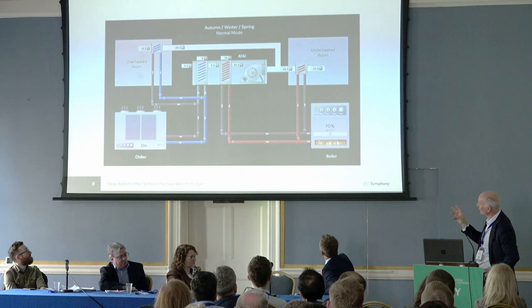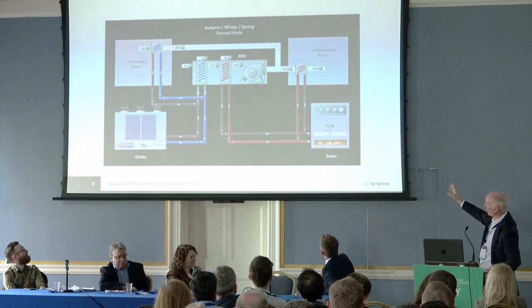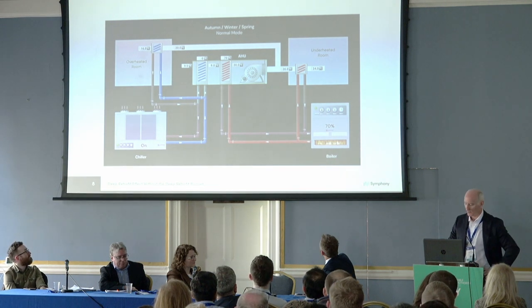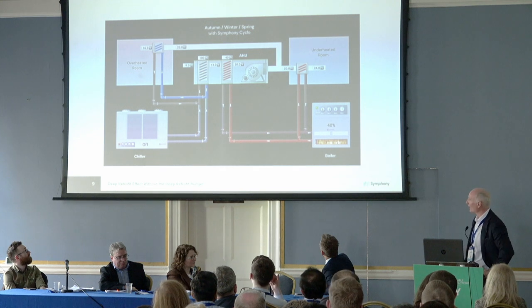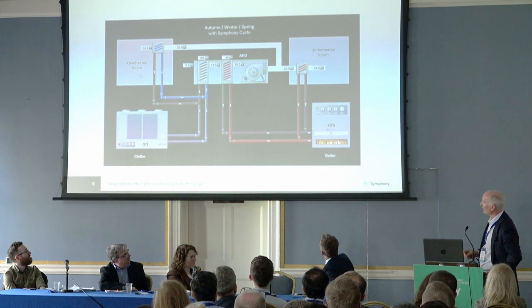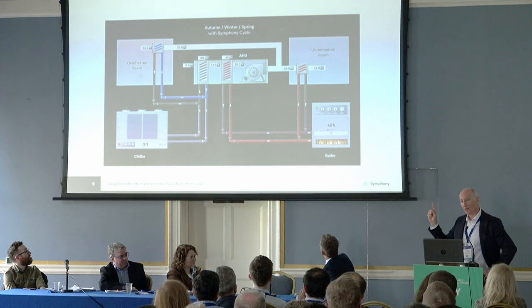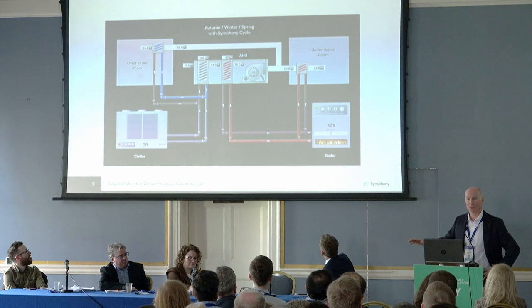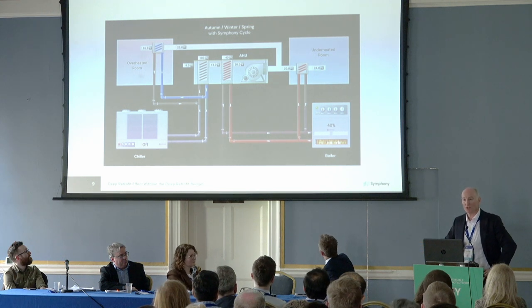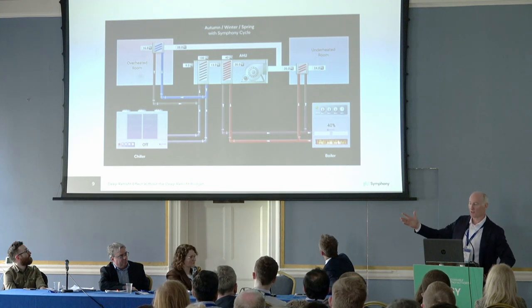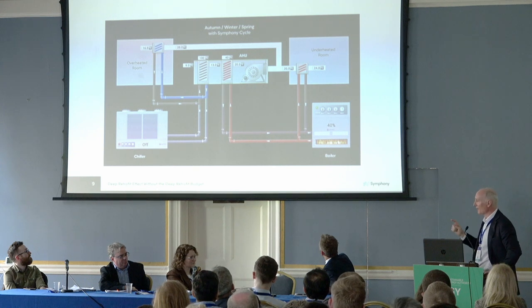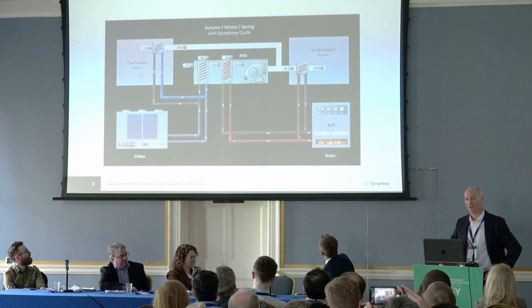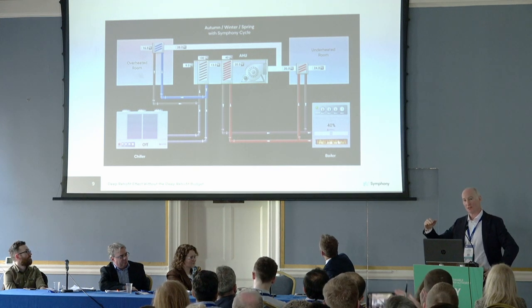So notionally, your chiller's on, and say your boiler's at 70%. Introduce the heat recycling process, and what we do is completely counterintuitive. Your cooling coils in your air handling units are redundant outside of summertime. You don't need to cool your air if it's not summertime. However, we recognize that outside of summertime, your chilled water temperature can be allowed to drift up a little bit because it doesn't have such a high load to deal with.